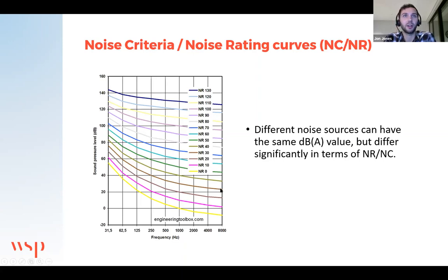These contours, if you look on this graph, essentially represent equal sensitivity or equal perception of a given sound. So as you move from right to left, where the right is high frequency and the left is low frequency, the amplitude of the sound has to increase to match a constant level of perception. So when we are considering acoustic criteria for rooms, perhaps in relation to building services, these curves are often used as a criteria level. I'll take the blue in the middle here, NR70, or it could be NC70. This would then become the noise target that we're looking to achieve.